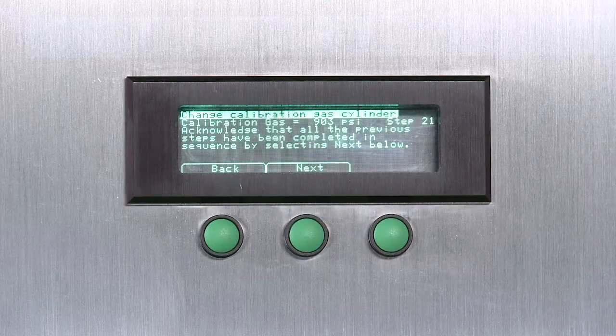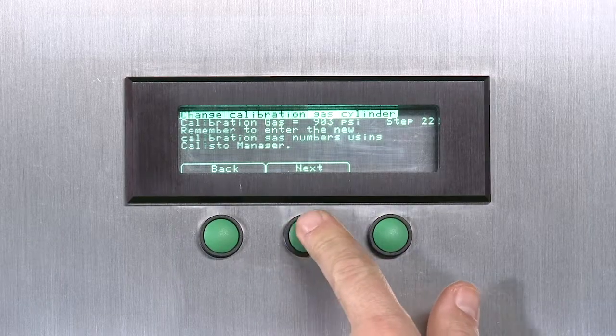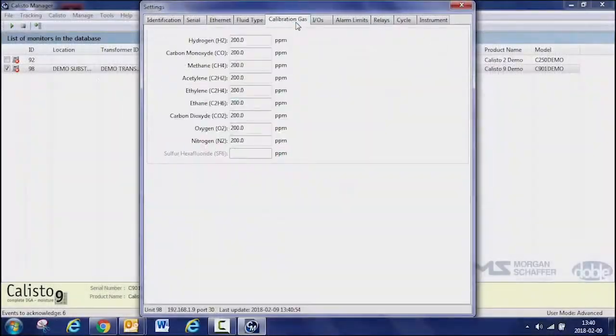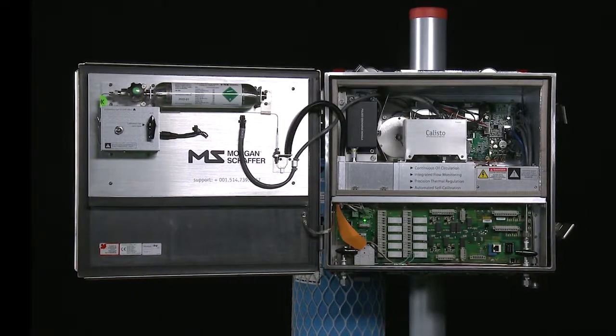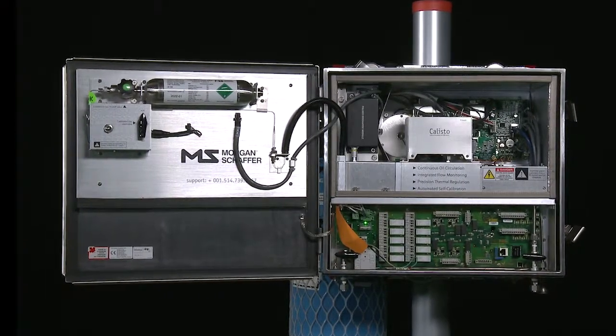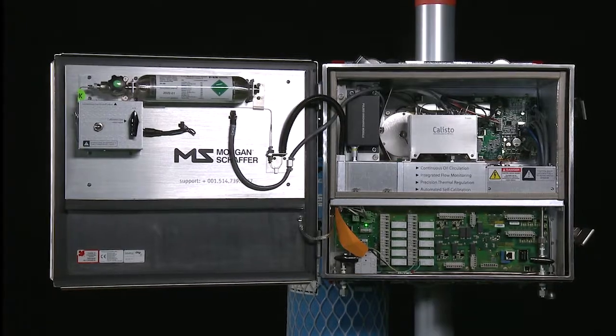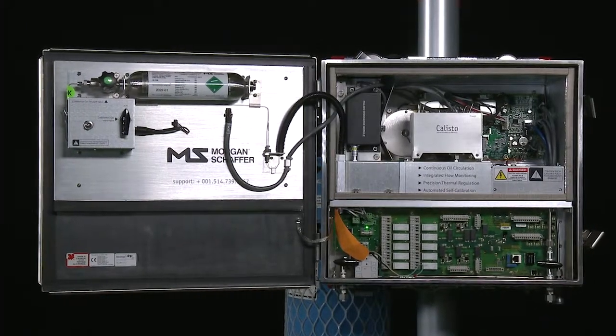Acknowledge that all the previous steps have been completed in sequence by pressing Next. Remember to enter the new calibration gas numbers using Calisto Manager. Note that this step will be explained in the configuration video. The calibration gas cylinder change is now complete. The unit will automatically resume operation in about 1 hour.